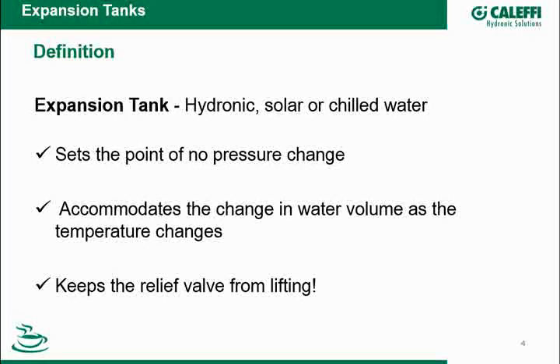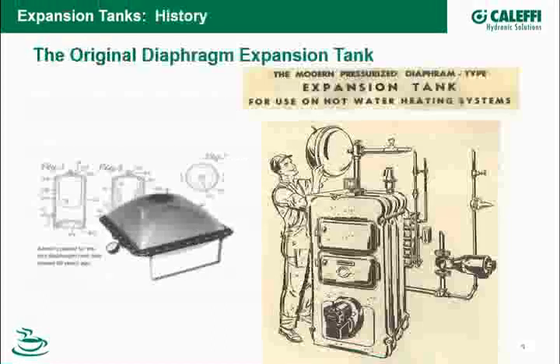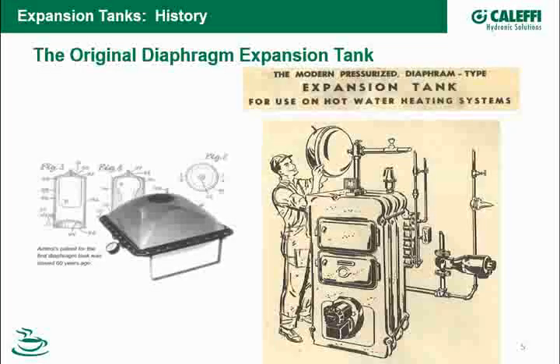Now, expansion tanks have been around for a period of time. If you look at what's on the picture here, the original diaphragm expansion tank is the tank that's shown on the left-hand side. It was an original patent by Amtrol 60 years ago. So it's not a new concept with the expansion tank. It came into the market to compete against what's called the compression tank and kind of address some of the issues that the compression tank has.